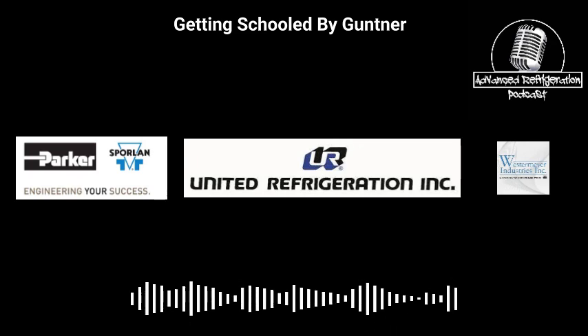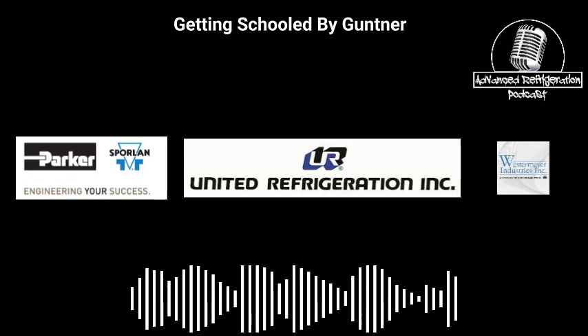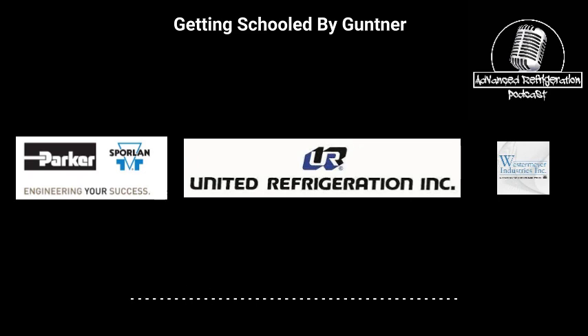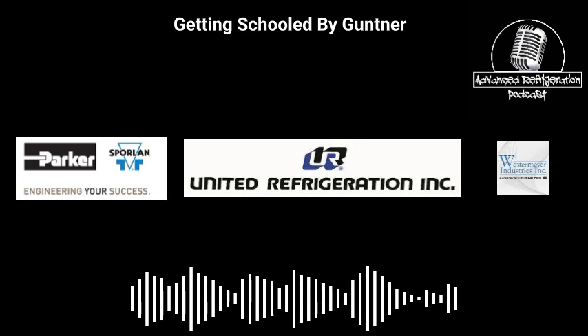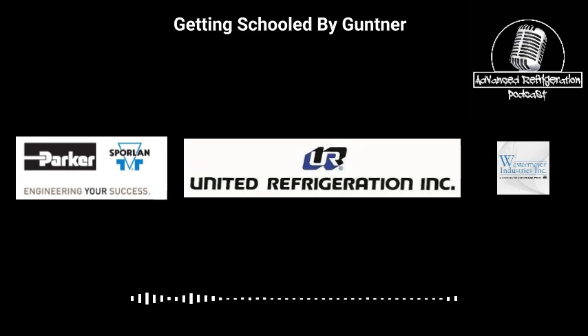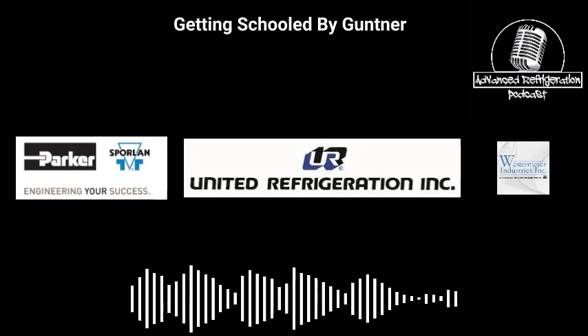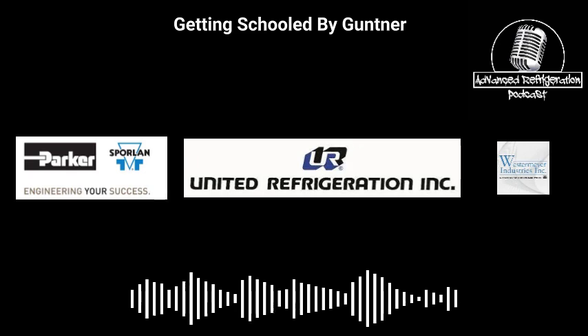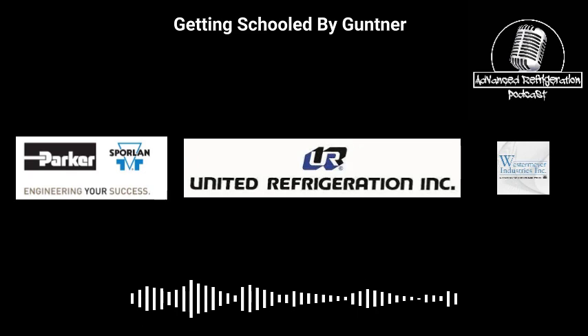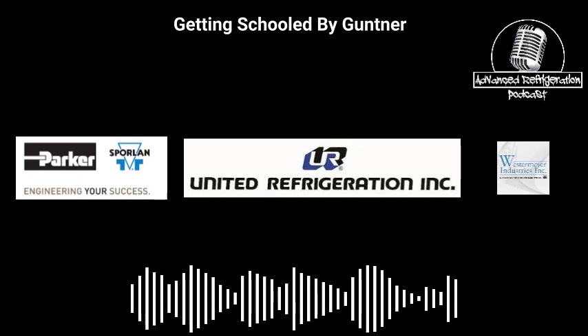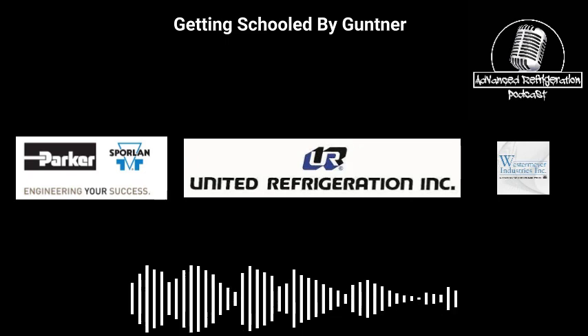No way. Yeah. So another question I had. I'm looking at the layout, right? And I know this isn't exactly how all the fans go, but Kevin, because he deals with a lot of lower ambient, being up in Chicago and Indiana and all those other cold places, a lot of times you'll start logging a little bit of gas in there, especially if a split function wasn't set up to be done. Is there any way in your controller to either disable half of the fans, or are there relay outputs on that controller that control each individual fan?